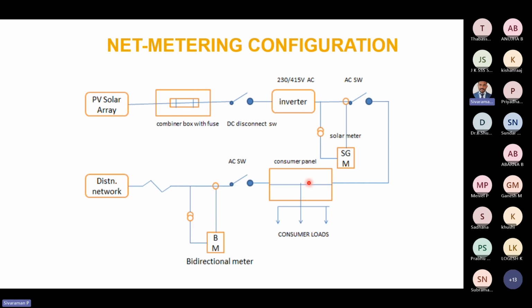So in our residential rooftop we are installing this solar PV system - up to this portion will be the solar PV system, including solar PV panels, then combiner box or DC distribution box, then solar inverter, and solar generation meter. Suppose if we want to calculate how much amount of solar power is generated, then we can install this solar generation meter. This meter can be installed in addition to the existing bidirectional meter. So the bidirectional meter is mandatory, this solar generation meter is optional - if you want, you can install it, or else you can ignore it. So this is the purpose of net metering.